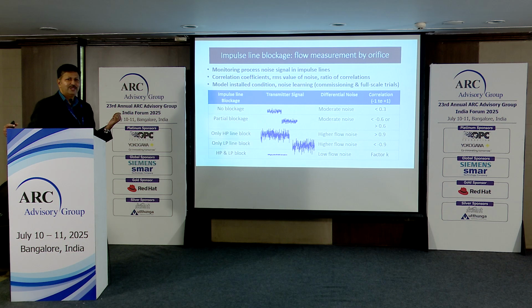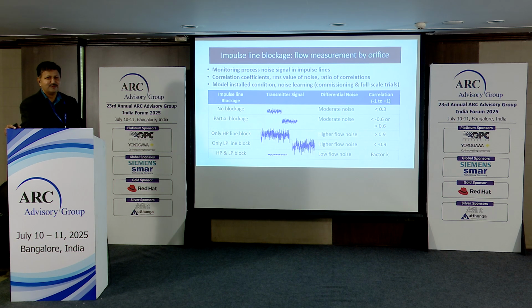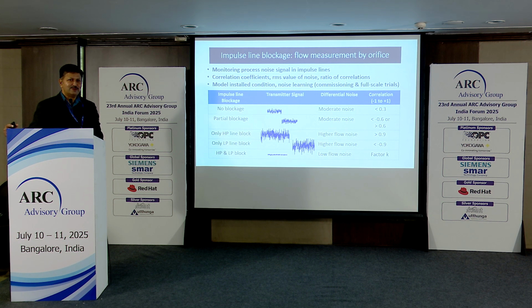Now where the AI actually comes into play is, these DP transmitters for flow measurement could be there in your piping in the field with a valve upstream, so there is an acoustic noise traveling inside. Or it could be in a situation where it is vertical and you have to take care of probably two-phase flow or the frequent entrapment of air in the impulse tubes, or vice versa. Or there could be such other situations. Maybe a pump is switched on or off, or there are such noise sources in the vicinity that can also be captured, or maybe the vibrations in the piping can also come in as noise. So that is where you need a learning or a training phase when you do an installation in the field, and that could be done as part of your installation commissioning trials and learning trials, right?